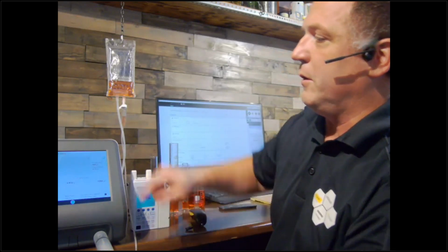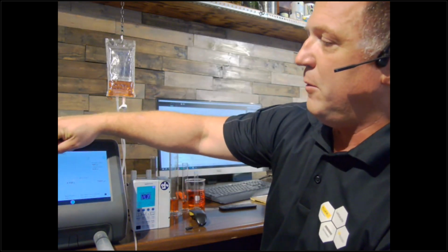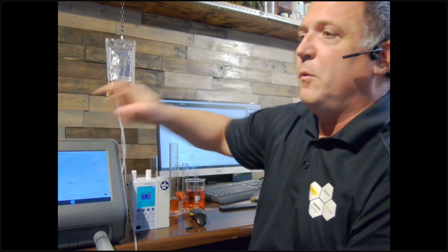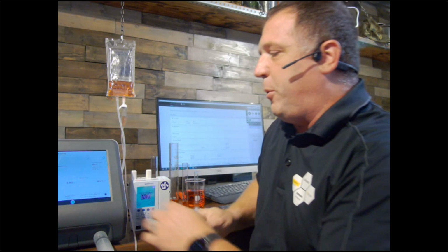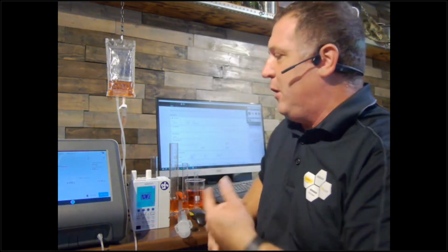You'll notice we have two lines: an instantaneous flow and an average flow. The point of that 30-minute test isn't to check immediate accuracy, it's to check what happens to the pump after the internal mechanisms warm up, what happens to the battery, and whether there are any dropouts. Like an older car where a clink or clank goes away once the engine warms up, that's why these prolonged tests exist, to make sure it can sustain performance. But if you want to see your flow at any point in time, you have both your instantaneous flow and volume as well as your average flow, so you can see them both.